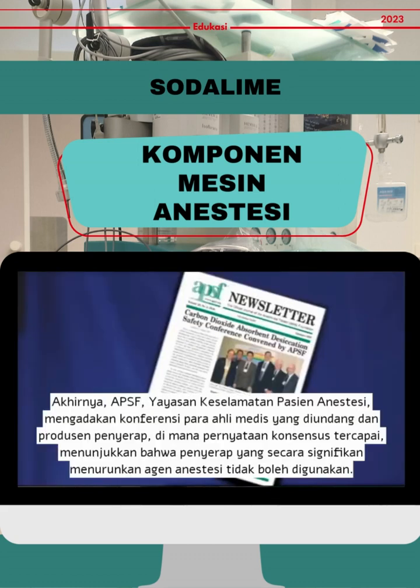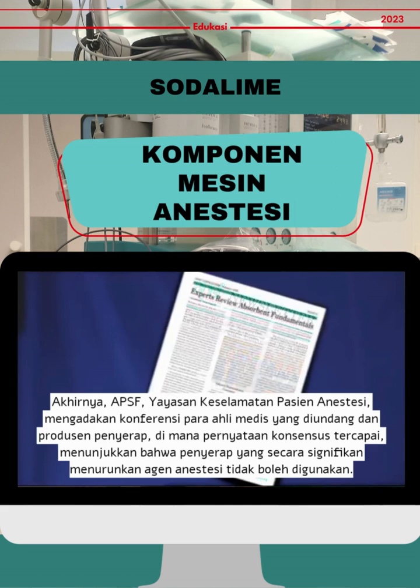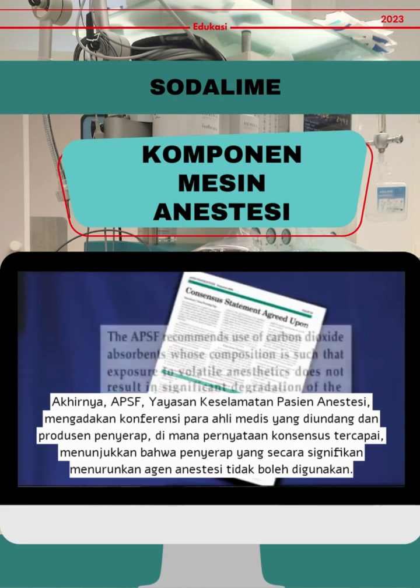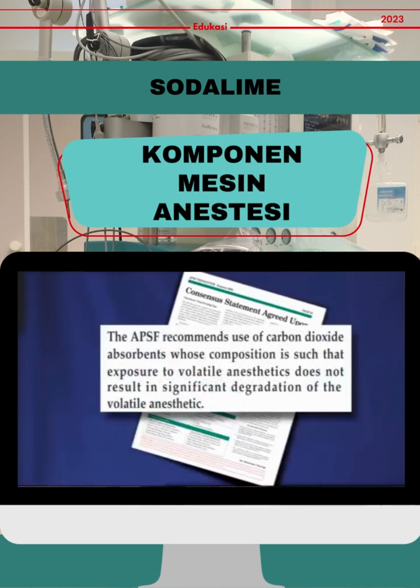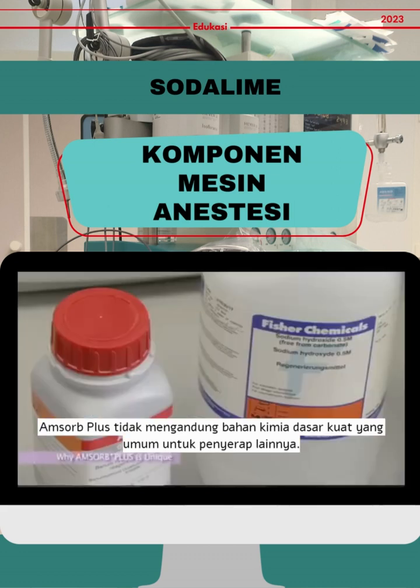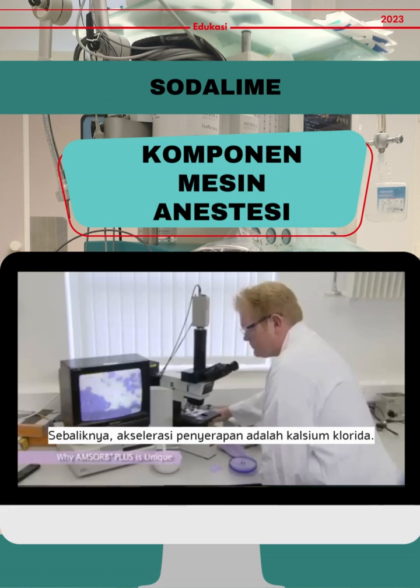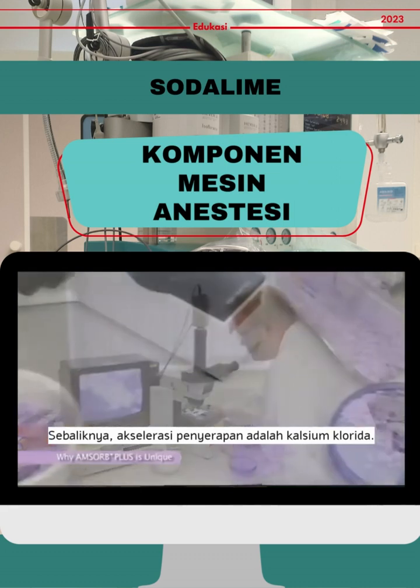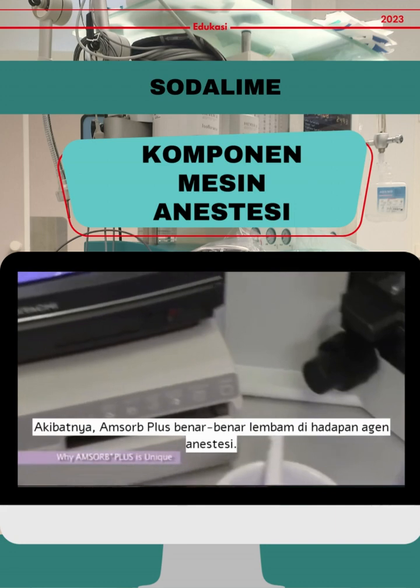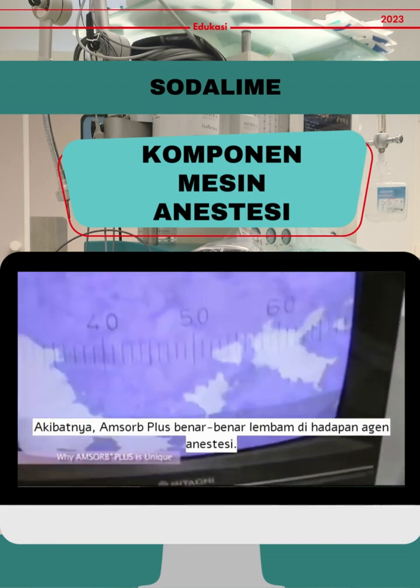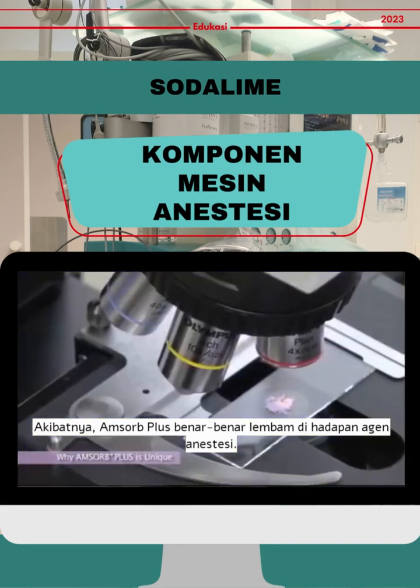Finally, the APSF, Anesthesia Patient Safety Foundation, convened a conference of invited medical experts and absorbent manufacturers in which a consensus statement was reached, suggesting that absorbents that significantly degrade anesthetic agents should not be used. Amsorb Plus does not contain strong base chemicals common to other absorbents. Instead, the absorption accelerant is calcium chloride. Consequently, Amsorb Plus is completely inert in the presence of anesthetic agents.